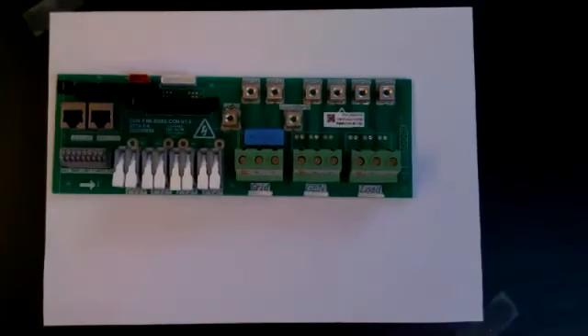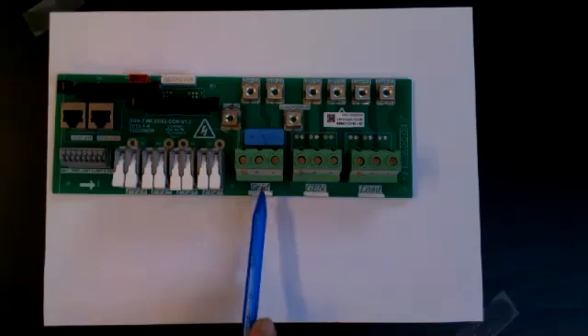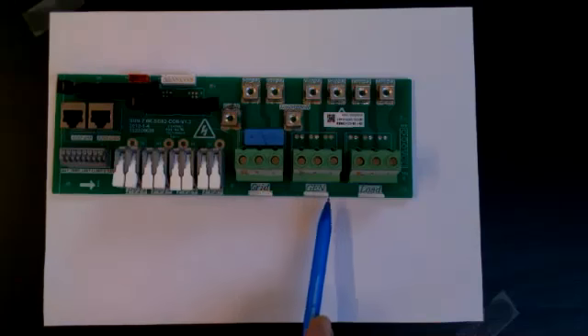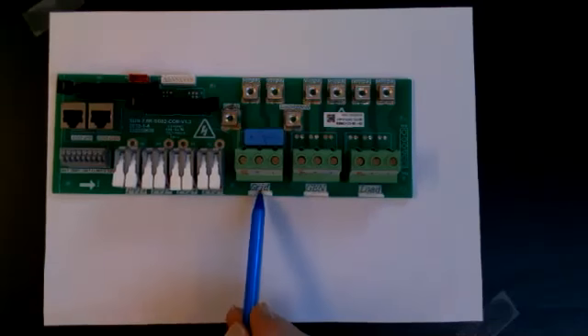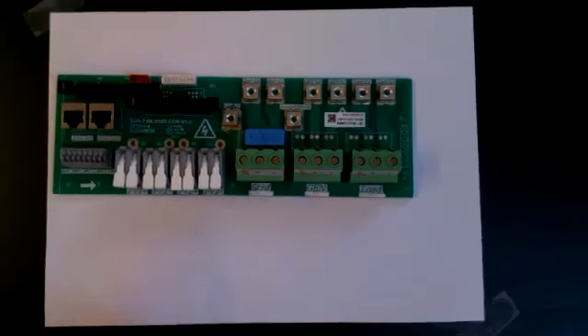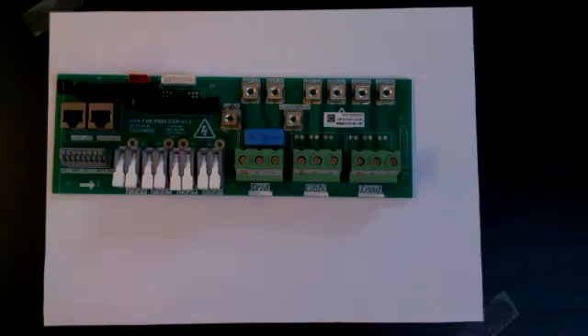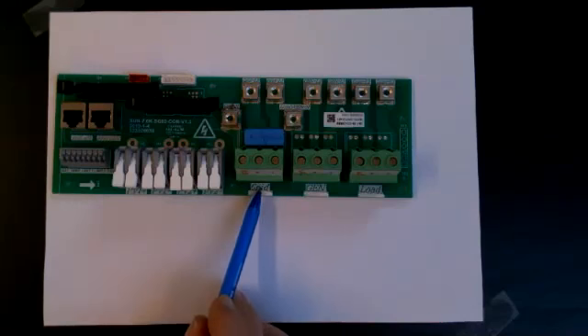So this is the board off an 8 kilowatt, but they're all pretty much the same thing. And you have a grid connection, you have a generator connection, and your load connection. The grid is both an input and an output. It's the same connection. If you're working off grid and you're not using a battery, you're using it as an off-grid inverter, you only connect to the grid connection. And this is both in and out.